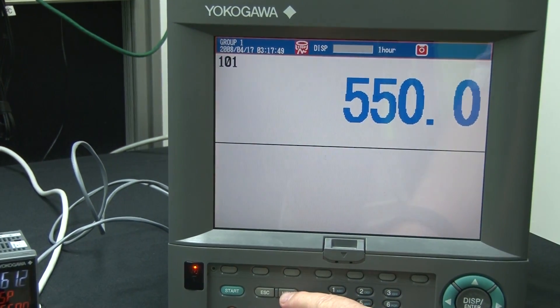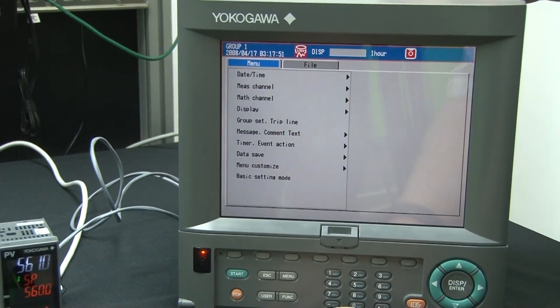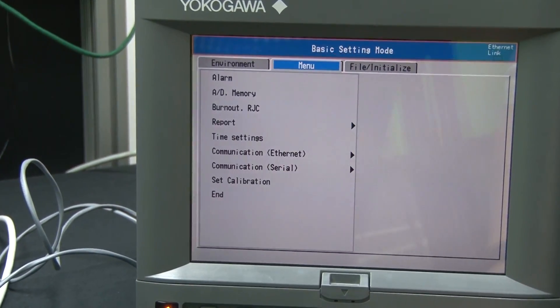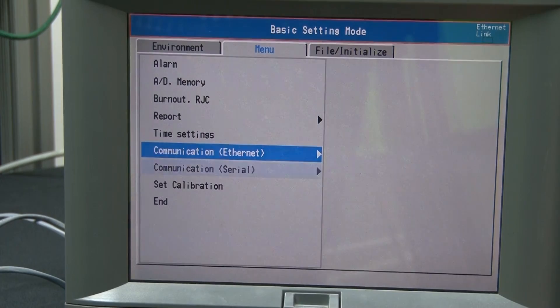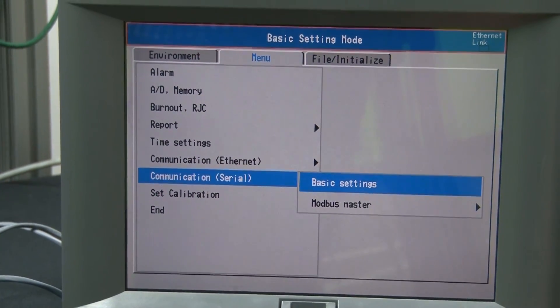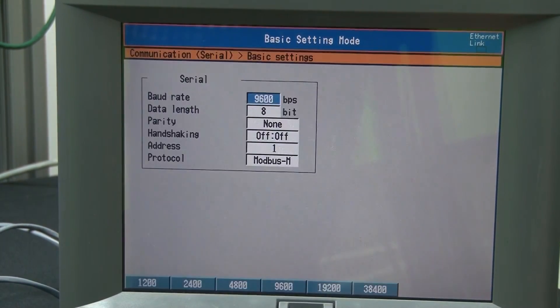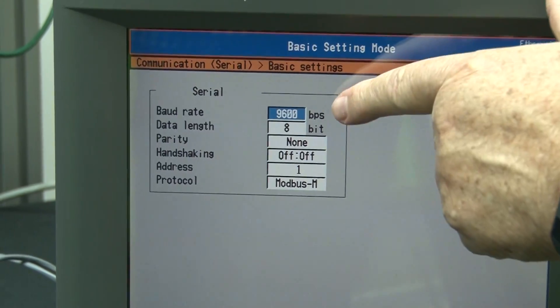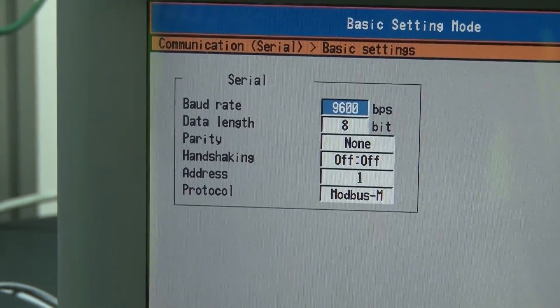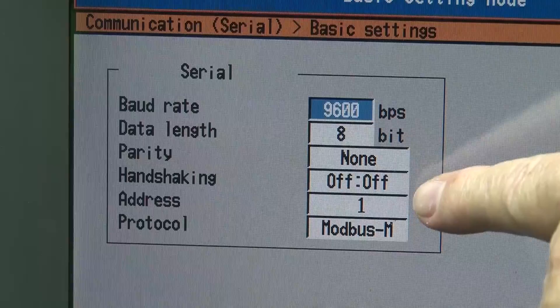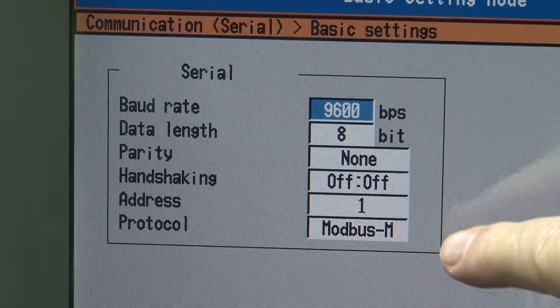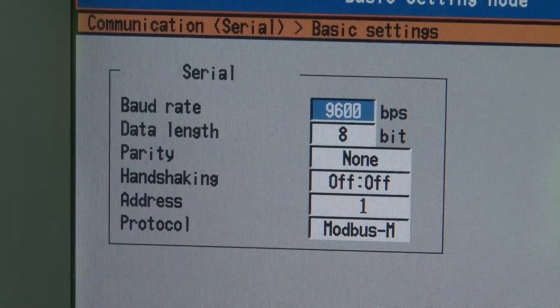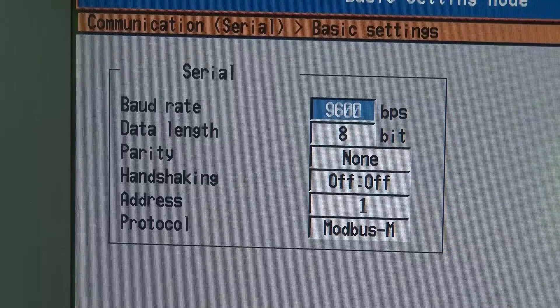In the recorder we have similar settings, found in the basic setting menu under the communication serial menu. Looking at the bus basic settings, we see the 9600 baud rate, the 8-bit data length, and no parity. There's also handshaking, which is not really used in RS-485. The address of the recorder is address 1, and it's set for the protocol of Modbus Master.